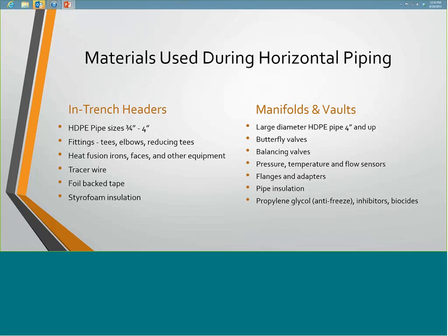Typically, you won't see a lot of pipelines bigger than 12 inches in geothermal. We use a lot of butterfly valves, one at every point where a header connects to the manifold. Balancing valves are generally installed on each connection. Pressure, temperature, and flow sensors are also used, and as DDC controls continue to evolve, there's more digital interface with these systems for monitoring their health. You'll also see flanges, adapters, a lot of pipe insulation, as shown in a previous picture, and propylene glycol.